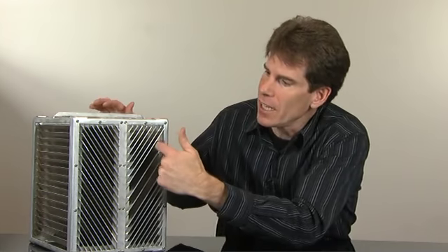So if this were every plate in place and we pulled it out, now instead of, say, a 1/4 inch gap or 1/2 inch gap, we could double that to 1 inch. We can go from 5/16 inch right angle gap all the way up. So that translates into 1/2 inch gap increments vertically. So as you can see here, much more gap in this area than this area. This will foul less. This is going to be more efficient. So by pulling every other plate system out here, we've changed the fouling characteristics of the plate pack.